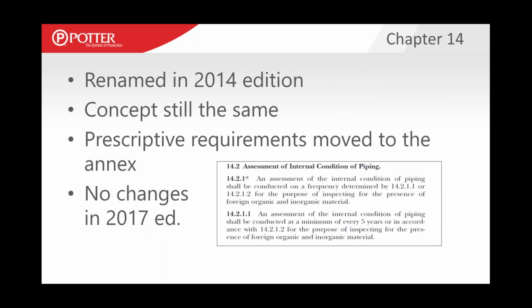So I told you that the internal inspection has changed. What happened in the 2014 edition was that the task of opening up the pipe changed. It's renamed now assessment of internal condition, as opposed to being an internal inspection. In other words, the hard prescriptive requirement to open up the pipe and look inside it every 5 years changed. Now what's required is an assessment of the internal condition. The concept behind it is still the same, but the prescriptive requirements to remove a sprinkler from the end of a branch line and open up a flushing connection at the end of one main, that was required in the past. Those have moved to the annex.